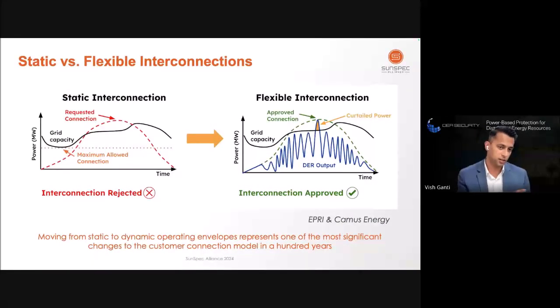So here is a view of the historical approach with static connection limits. What you see on the left side is effectively a static interconnection limit when the grid capacity is lower than what the site is requesting. Normally, the utility would do a study and say we cannot approve this site to come online unless you change the way the site is operated, or reduce the load, or reduce the amount you're requesting. This is done because the grid is not ready - it's probably having congestion problems, or the transformers and other network equipment need to be upgraded to support the requested load.